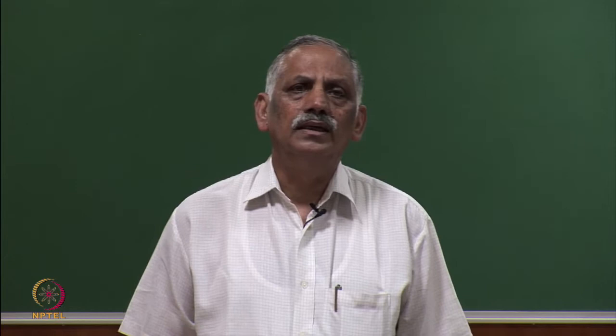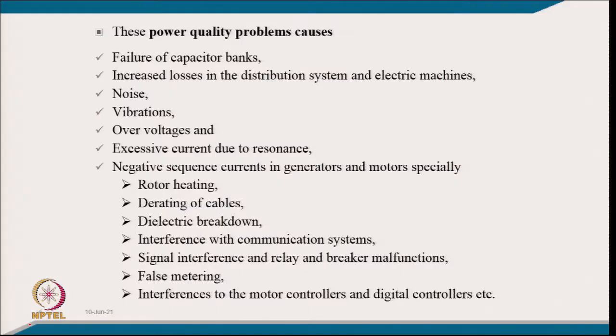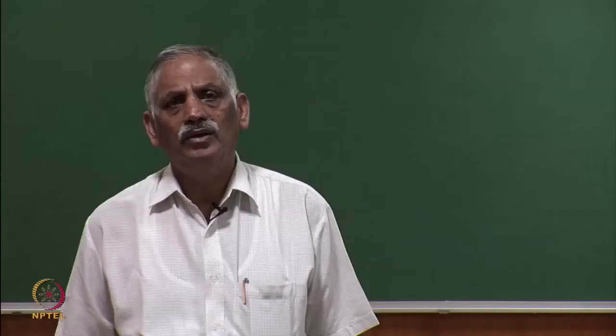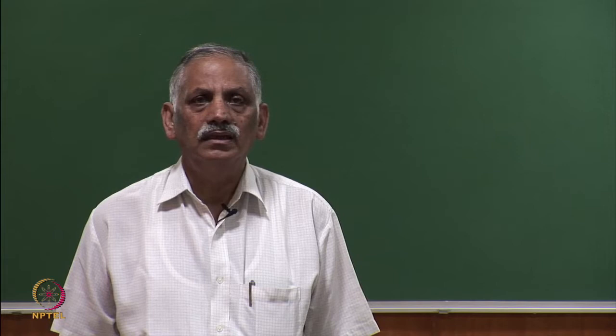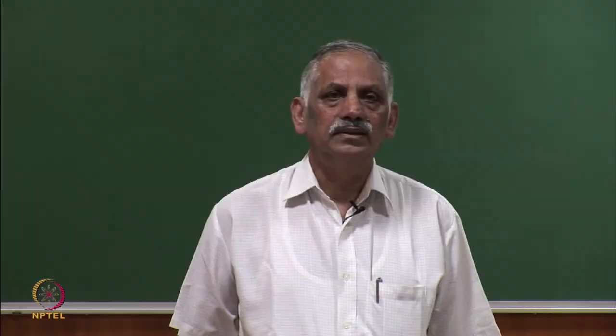Power quality problems cause derating of cables because more current is drawn compared to the fundamental for which most distribution systems and cables were designed. They also cause dielectric breakdown due to excessive voltage, interference with communication systems, signal interference, and relay and breaker malfunction.